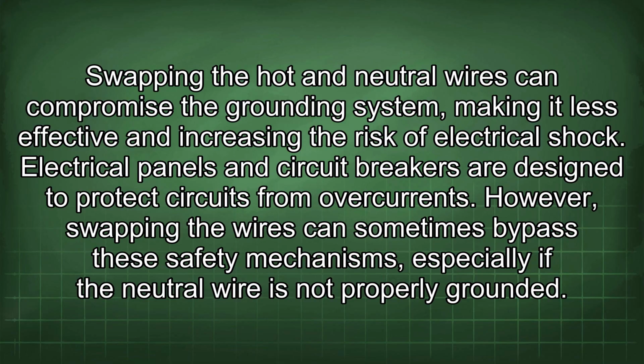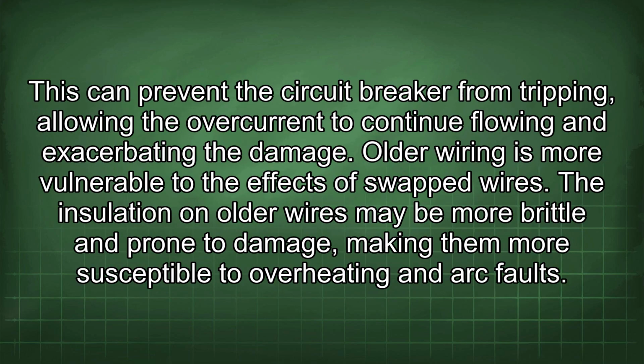However, swapping the wires can sometimes bypass these safety mechanisms, especially if the neutral wire is not properly grounded. This can prevent the circuit breaker from tripping, allowing the overcurrent to continue flowing and exacerbating the damage. Older wiring is more vulnerable to the effects of swapped wires.